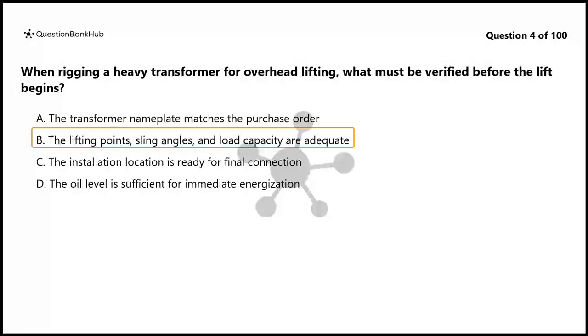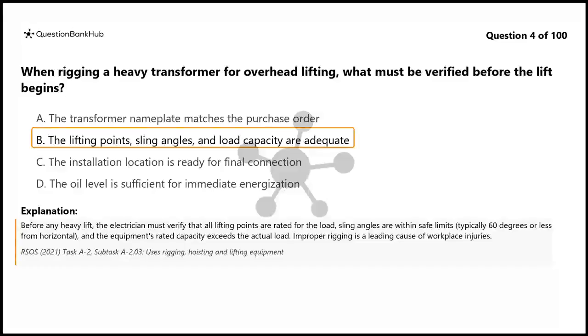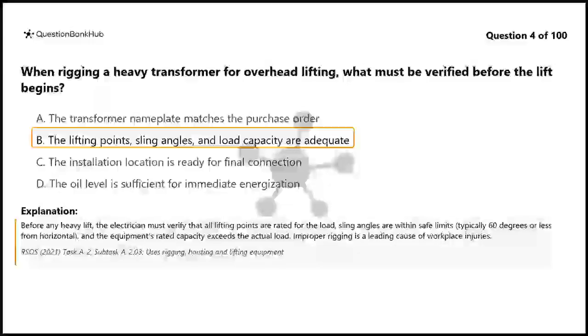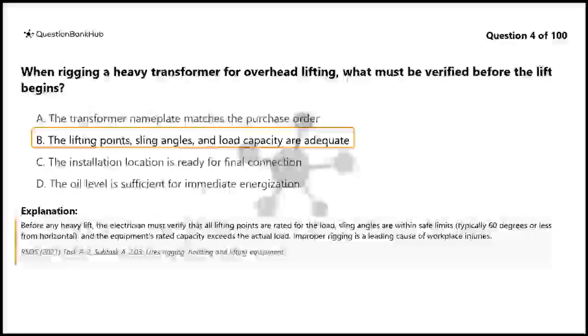The correct answer is B. The lifting points, sling angles, and load capacity are adequate. Before any heavy lift, the electrician must verify that all lifting points are rated for the load, sling angles are within safe limits, typically 60 degrees or less from horizontal, and the equipment's rated capacity exceeds the actual load. Improper rigging is a leading cause of workplace injuries.